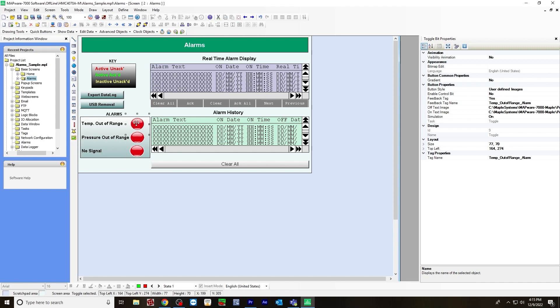When you click these on, the alarm will show up here in the alarm display. When the alarm is activated, it'll be red. Active unacknowledged alarm will be red and inactive unacknowledged alarm will be yellow. Active acknowledge alarm will be green. I'll show you that when we go online later on.